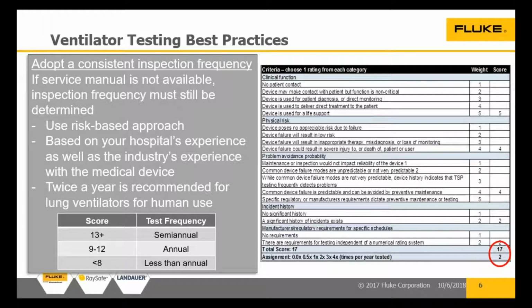Here's where we might take another NFPA 99 trick, okay, and say, well, in our policy statement, in our quality program, we will say, for these risk level of devices, we will test them on incoming inspection and make measurements and keep them, document them, and we will do post-repair, same thing, but in between, we're on a run till fail strategy. Run till fail. Now, keep in mind, we can't do run till fail on all of the devices. The regulators will not let us, and that's a good thing. Because there are a lot of us, unfortunately, who would just do everything run till fail.